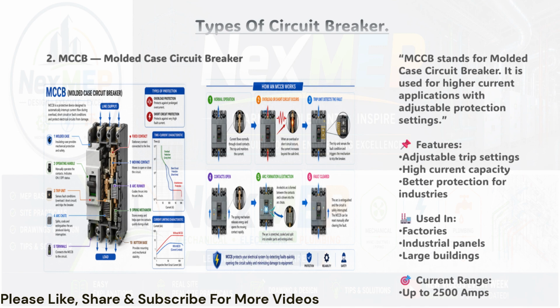This makes them extremely flexible for industrial use. The MCCB works by detecting an overload or short circuit, tripping the mechanism, and extinguishing the arc in the arc chute. But due to the higher current levels involved, the internal design is much more robust. The spring mechanism releases energy quickly to open the contacts and handle the arc safely.